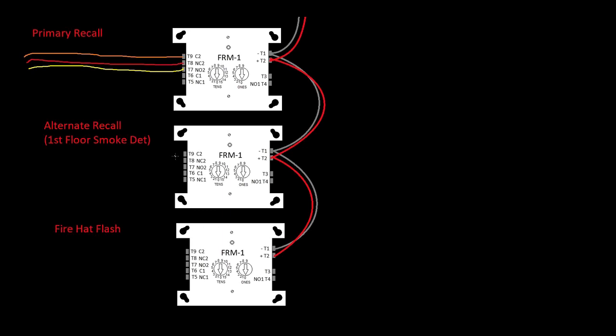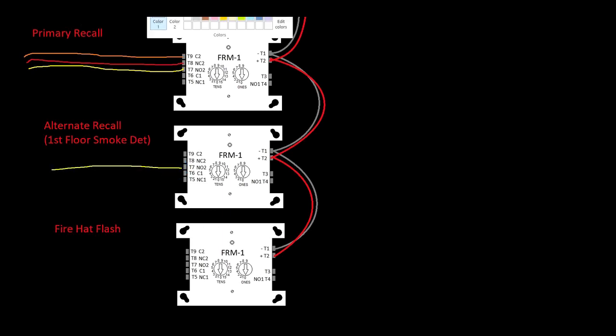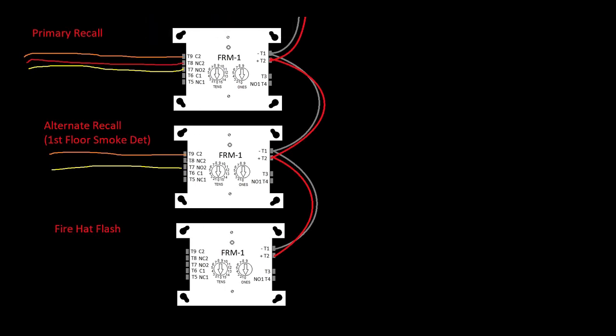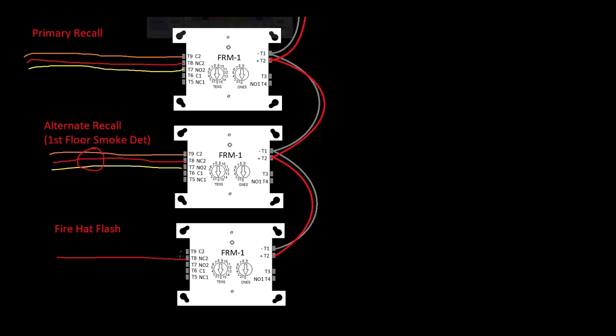So I would just repeat this, I'd use probably even the same colors of wire because you're probably not going to have nine different colors of wire. Label that for them. I would label this floors two through four and basement. I would label this, you know, do the same thing, label each individual wire and label what it does. Because what I mean, right here it's really easy to see, but once these are all going through conduit in their equipment, you're going to have tape around the pairs, so like this, you know, this three are all taped together. Label each individual wire - common, normally closed, normally open - and label it what it does, you know, so that they know.